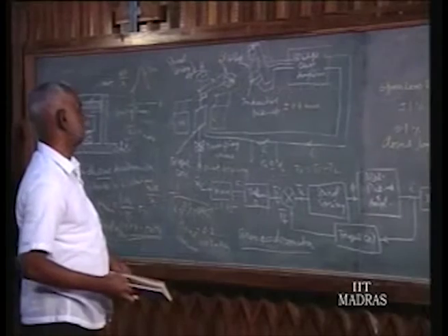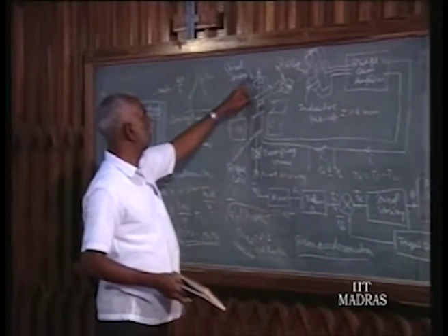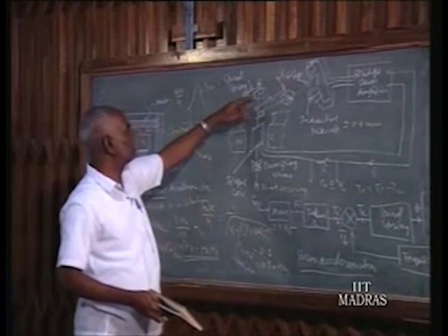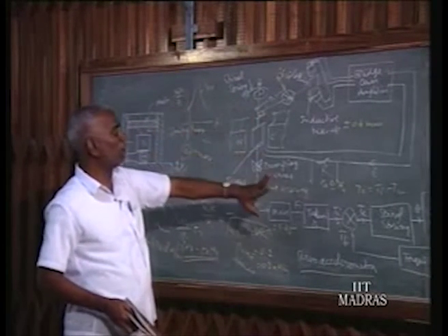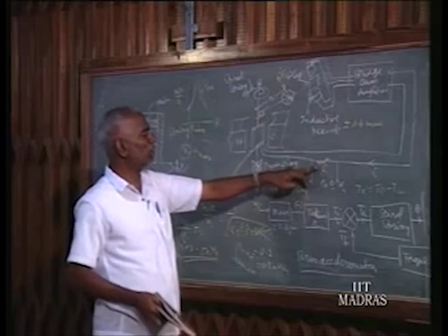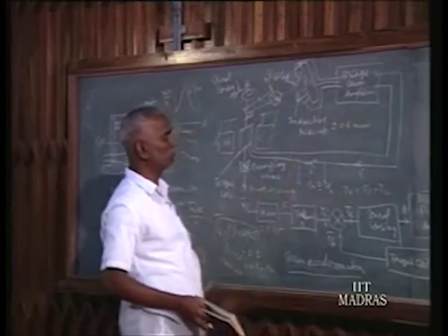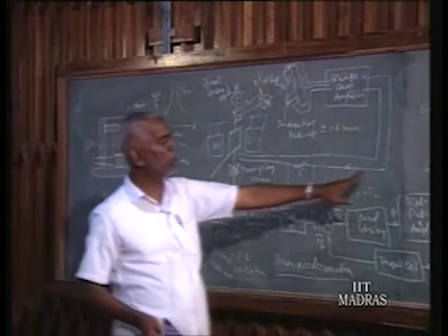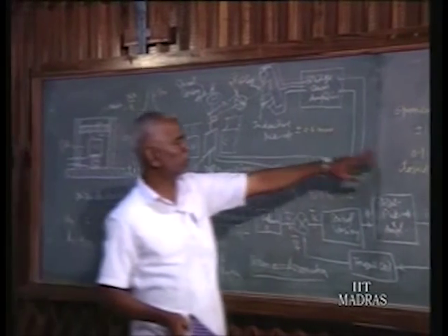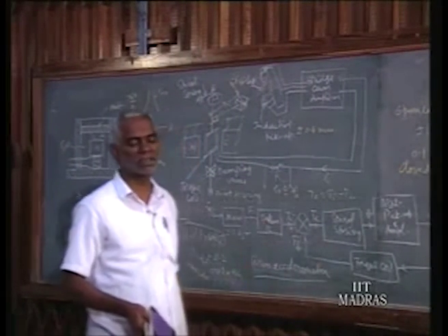All advantages associated with a closed loop system are there. In an open loop system, if the temperature rises, the spring constant will come down, and then it will show a higher reading. But to bring it back, we require only a smaller current. That's why the error is eliminated in any closed loop system. Hence, closed loop systems are generally more accurate than open loop systems. Up to 0.1% or even less than that we can obtain, depending upon the elements you have selected.